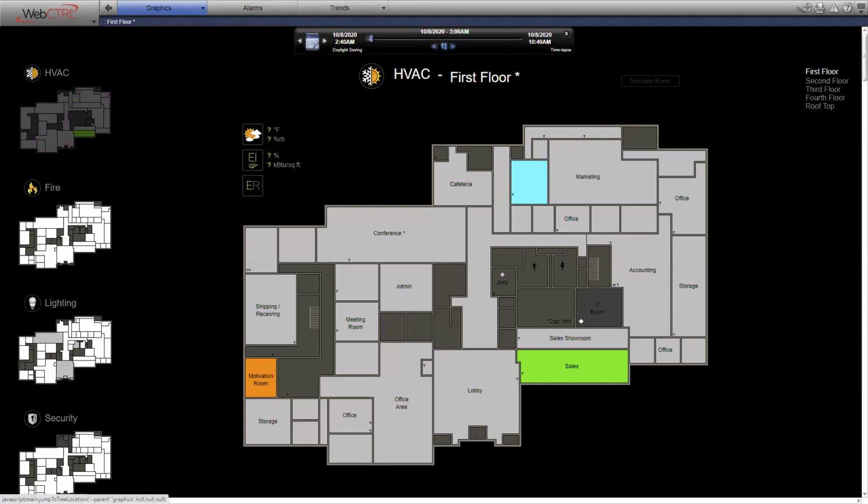And what we'll see, remember I said when the zones are unoccupied or under control of unoccupied set points, the zones would show up gray. You'll notice the majority of the zones are showing up gray. It's now 4:30, 4:50, 5:10, 5:20, 5:30, and we're beginning to see the zones come in the optimum startup routine. And here we are at 8:20, and we see all the zones active. It's a great diagnostic tool.